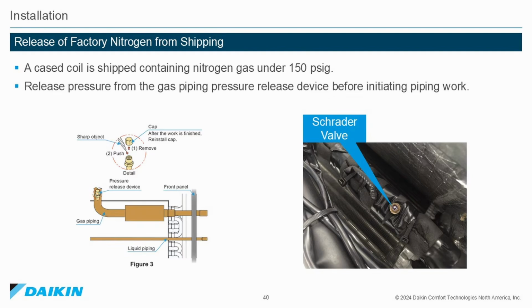Release of factory nitrogen from shipping. A cased coil is shipped containing nitrogen gas under approximately 150 psig of pressure. Release pressure from the gas pipe pressure release device before initiating piping work.